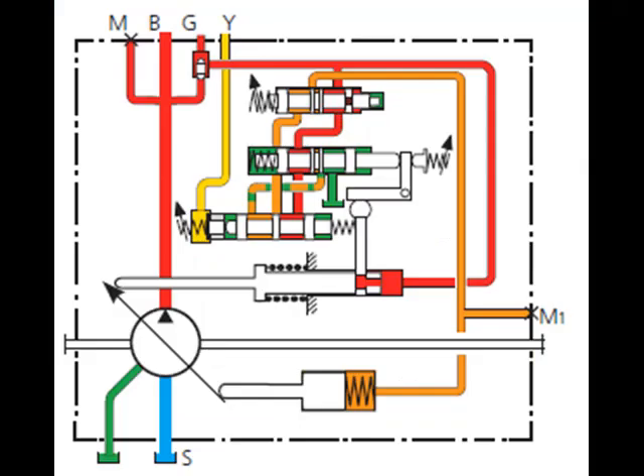LRE Power Control with Pressure Cut-Off, 2-stage. By connecting an external pilot pressure to port Y, the basic value of the pressure cut-off can be increased by 50 ±20 bar and a second pressure setting implemented. This value is usually above the primary pressure relief valve setting and therefore disables the pressure cut-off function. The pressure signal at port Y must be between 20 and 50 bar.